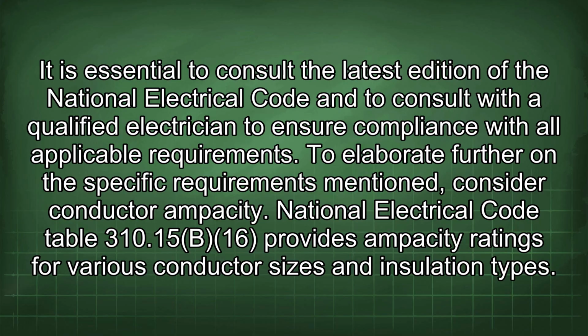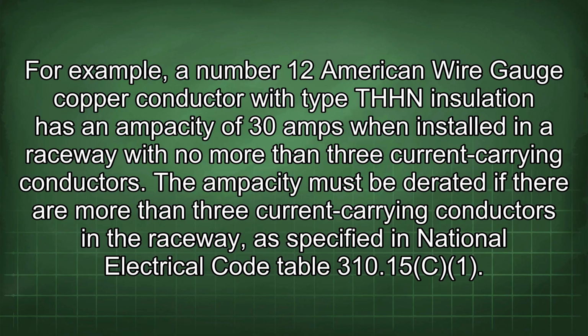To elaborate further on the specific requirements mentioned, consider conductor ampacity. National Electrical Code Table 310.15(B)(16) provides ampacity ratings for various conductor sizes and insulation types. For example, a number 12 American wire gauge copper conductor with type THHN insulation has an ampacity of 30 amps when installed in a raceway with no more than 3 current carrying conductors. The ampacity must be derated if there are more than 3 current carrying conductors in the raceway, as specified in National Electrical Code Table 310.15(C)(1).